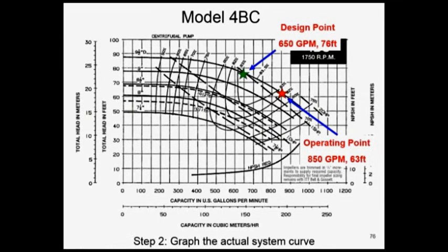The first thing is, what is the actual system curve? Not what was specified. What was specified was 650 at 76. We're not there. We turned the pump on, the discharge valve was wide open, and we read 63 feet at 850 GPM. Don't change any valves. That's what the real system is doing. You know, pumps are stupid. Systems are stupid. They don't read the specs. And this pump is actually putting 850 out at 63 feet of head. So that's the true system curve the way it's installed.